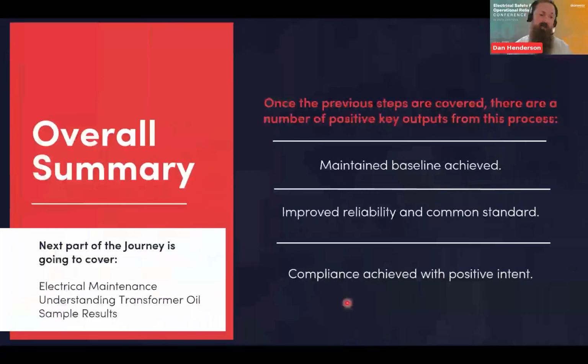So just to summarize, I'm just conscious of time. Hopefully it's given a bit of an idea around how to achieve a baseline standard condition from your maintenance perspective, but you might always slip back if you're not on top of it. And we're all human. So it's just trying to understand where you sit, then push the needle right and make sure you've got a reliable and safe network. Hopefully that'll give you improved reliability and achieve a common standard by following your local IEC process, NFPA 70B or the O&M manual, or a combination of all of those, whatever fits your geographical requirements, to make sure you've got compliance achieved with a positive intent.